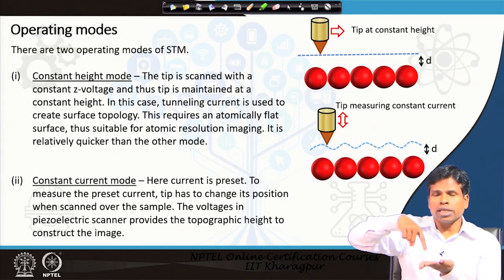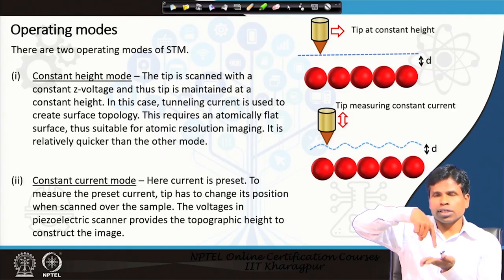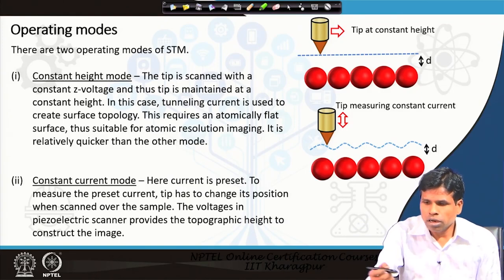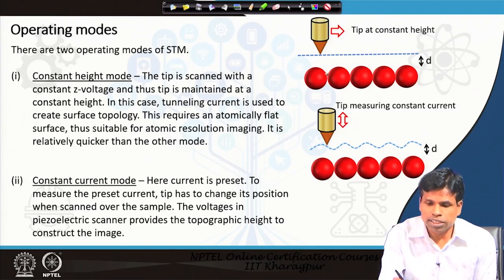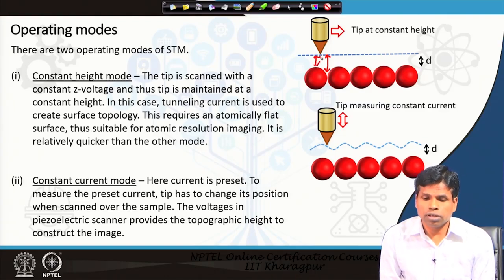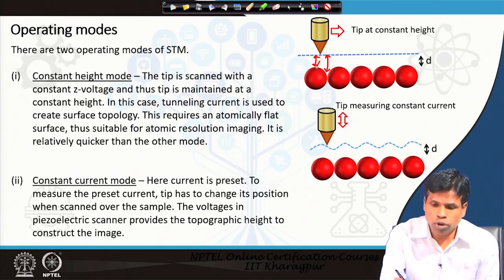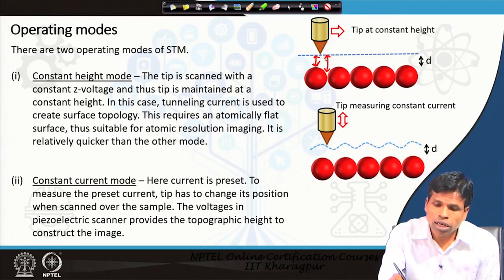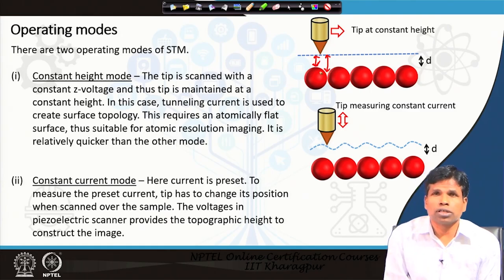As we move at constant height, if at any place there is a protrusion or hill on the sample, then our tip will be much closer to the sample surface. If at any place there is a downward valley, we will have a larger distance between tip and sample. So depending upon the sample height, the gap between the tip and sample varies — at some places the gap is larger and at other places the distance between tip and sample is smaller. When the distance is smaller, we measure a higher tunneling current; when the distance is larger, we measure a smaller tunneling current.